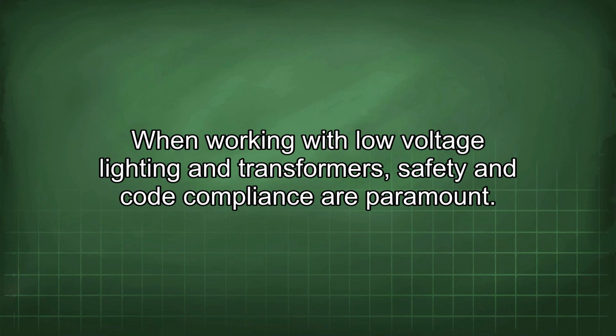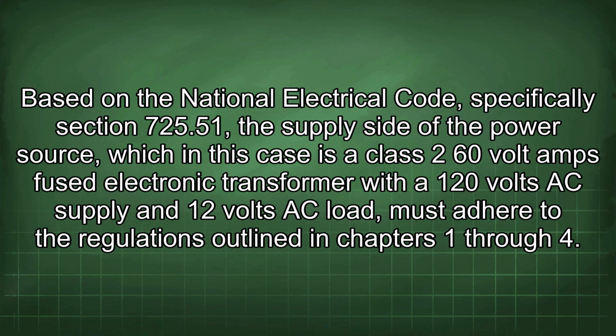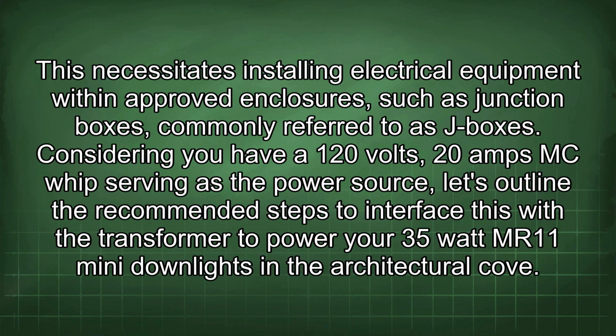When working with low voltage lighting and transformers, safety and code compliance are paramount. Based on the National Electrical Code, specifically Section 725.51, the supply side of the power source, which in this case is a Class 2 60 volt-amps fused electronic transformer with a 120 volt AC supply and 12 volts AC load, must adhere to the regulations outlined in Chapters 1 through 4. This necessitates installing electrical equipment within approved enclosures, such as junction boxes, commonly referred to as J-boxes.